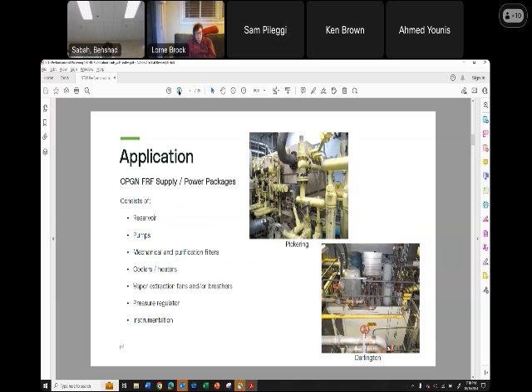Westinghouse and General Electric steam turbines use swash plate axial piston pumps, which vary the high pressure pump output according to system demand. And generally, those turbines do not experience chronic FRF degradation problems. Parsons and ABB use the screw pumps, which are constant volume, and they're constantly putting out full output and exhibit the high shear stress on the fluid, which degrades it very quickly.